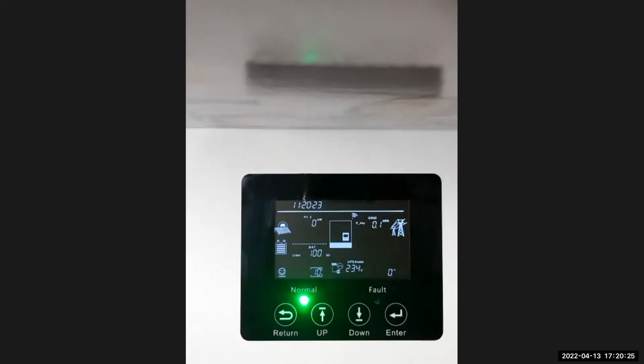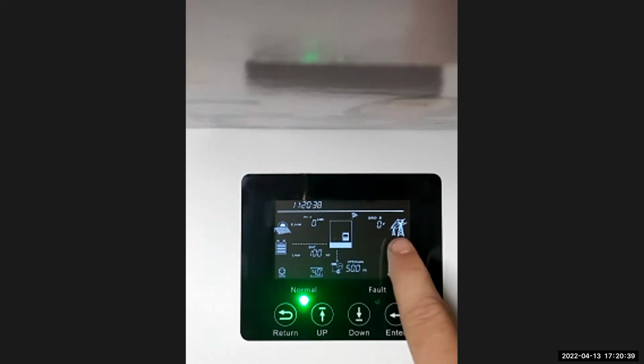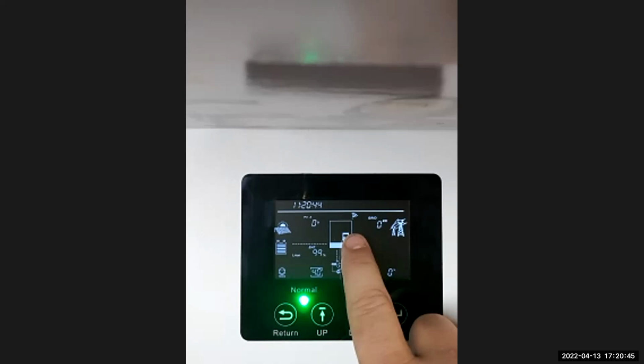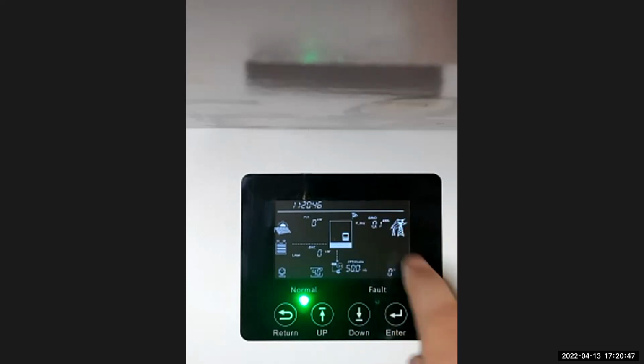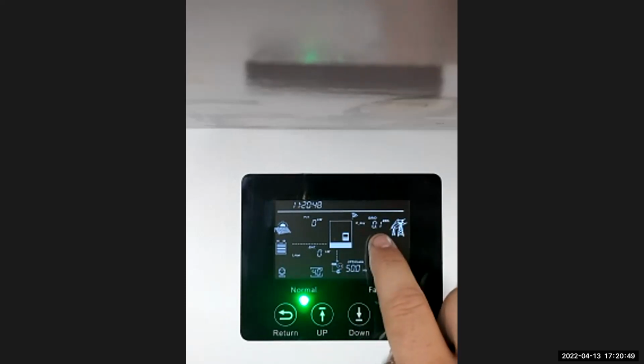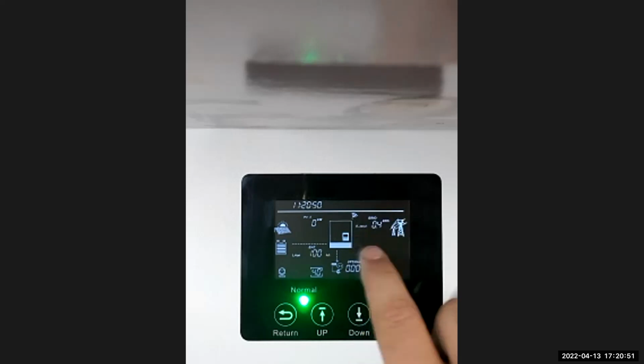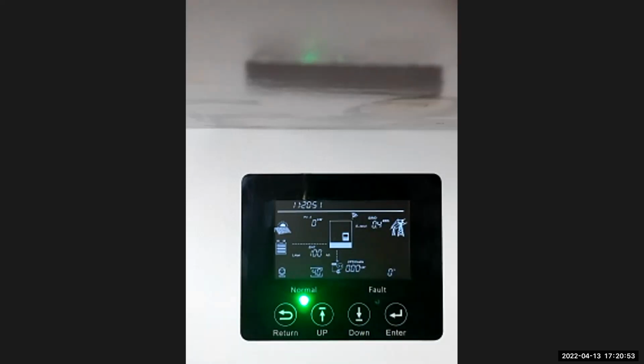Nice and clear. Okay, as you can see, I'm focused here on my screen at this moment. I'm going to switch off all my circuit breakers. So now basically my machine is running in off-grid mode. How you can tell that is you have no line between your AC sign that's here to your inverter. So you see there's no line there. And if you wait, you'll see it will show you 0 volts and hertz at this moment.